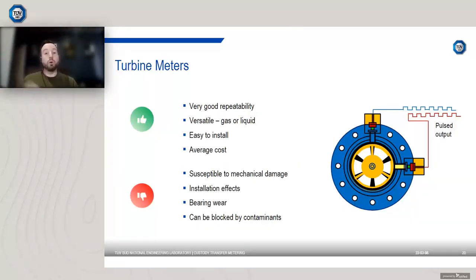Downsides are you've got a moving part, so they're susceptible to mechanical damage. Again, they're also sensitive to installation effects, so for these to work optimally, they need a nice, fully developed flow profile. And things like bearing wear can affect the ability of the rotor to spin, and they can become blocked by contaminants over time as well.